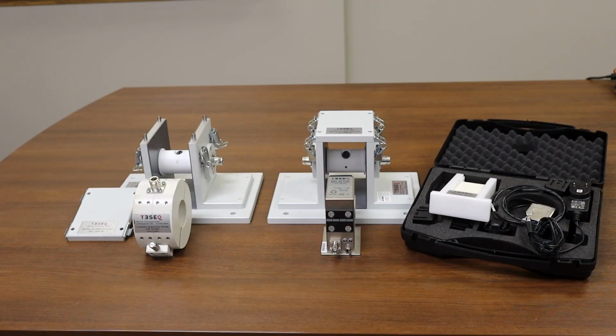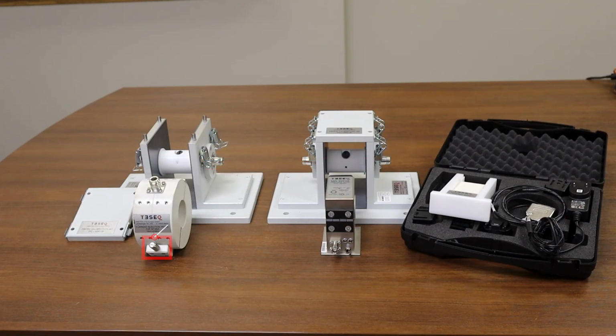The 9136A has a fixing screw which is turned to open the injection probe, and this is needed for when it's placed in the PCJ 9201B calibration fixture. The top of the calibration fixture can be removed to allow for the injection probe to be placed inside the fixture. The MD 4070A current monitoring probe and the related accessories are on the right.